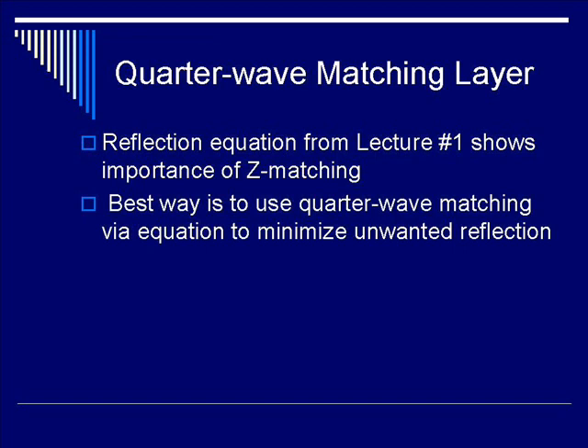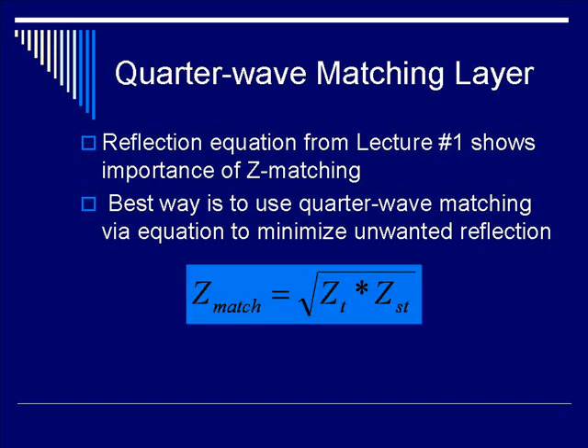The best way to minimize unwanted reflection is to use a quarter-wave matching layer via the equation as follows. Z of the matching layer equals the square root of the product of the impedance of the transducer and the impedance of the soft tissue.